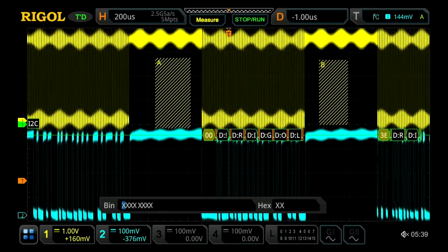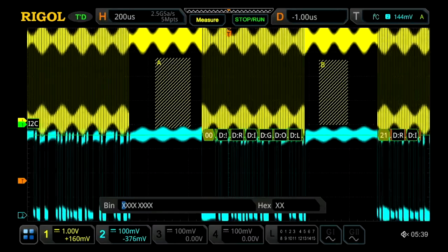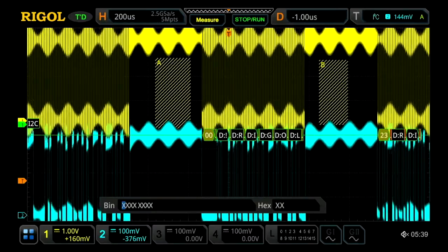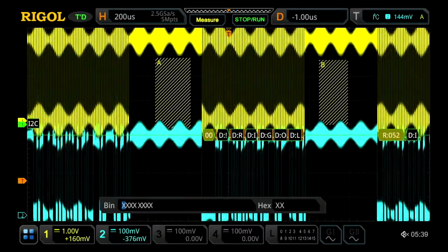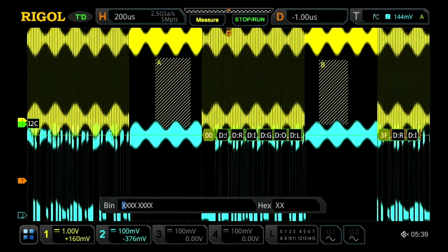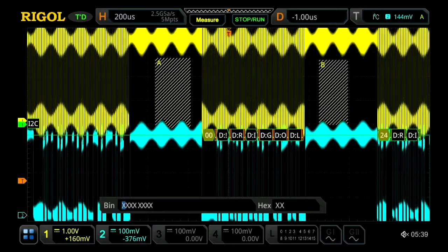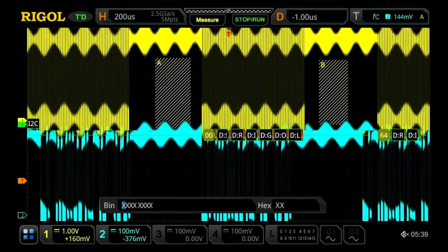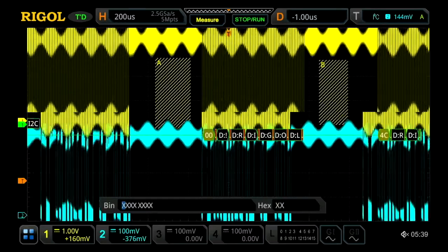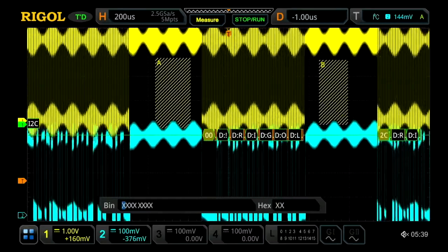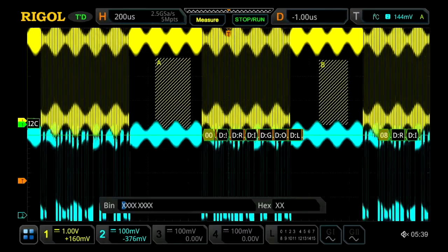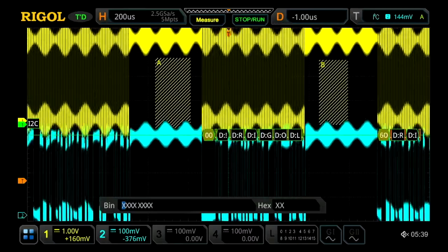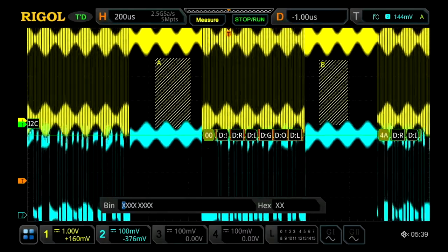So again, at plus 20 dBm, with the geometries of this cell, we're at just over 22 volts per meter field strength. We can see that clearly on the oscilloscope now. Some of that is certainly because we're picking up the modulation directly with the probes themselves. But it's also starting to affect the board at some frequencies. So this is how you test susceptibility on a device using a TEM cell.